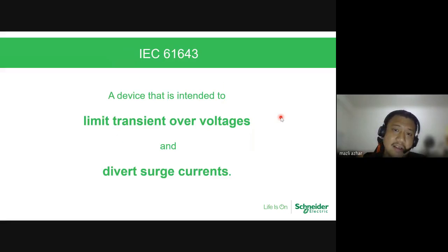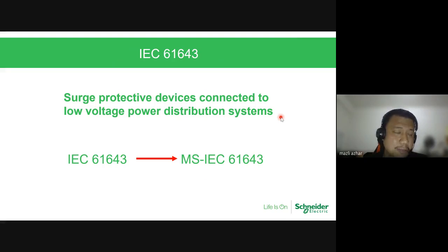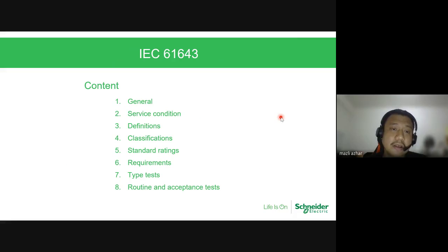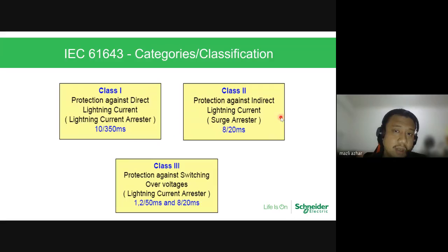Under IEC 61643, it is a device to limit transient overvoltage and divert surge current. Under the standards, it has been adopted as MS IEC. As usual, I will not go into depth, but any manufacturer, any brand, has to comply with this requirement: type tests, routine and acceptance tests, everything has to comply to ensure that the SPD is safe and performs as needed. So I will just go to the core things. You have categories and classification.